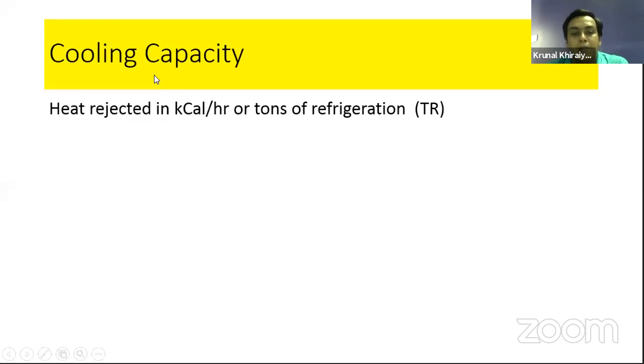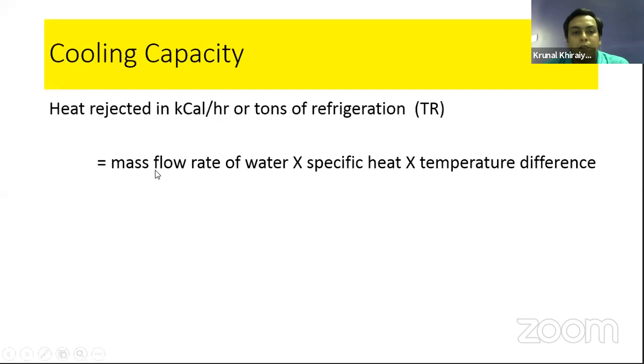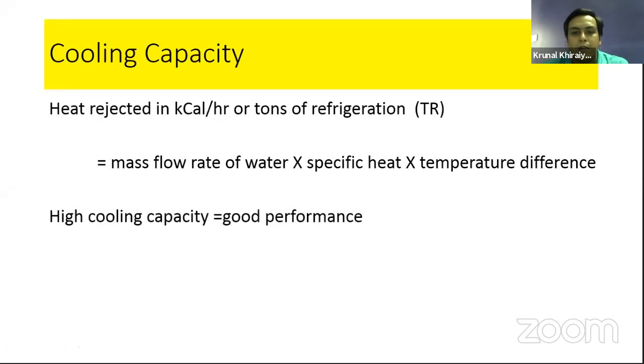Then cooling capacity. Cooling capacity is a very important term, because whenever students come from graduation into the industry, they don't even know in which unit the capacity of a cooling tower is measured. So cooling tower capacity is measured in tons of refrigeration, or you can express the capacity of the cooling tower in kilocalories per hour. So these are the two different units. How do you calculate it? Mass flow rate of water, specific heat Cp of water, and the temperature difference. It is a simple formula: m Cp delta T.